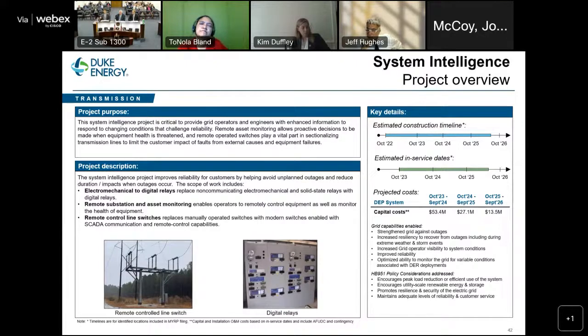We can use technology and algorithms to take the fault current that comes into our system, plug that into an algorithm, and determine the distance to fault. We can then dispatch the lineman directly to that location. They can assess the problem, determine if there's a switching solution, which I'll talk more about in another project area, or determine if there's a repair they can immediately make.